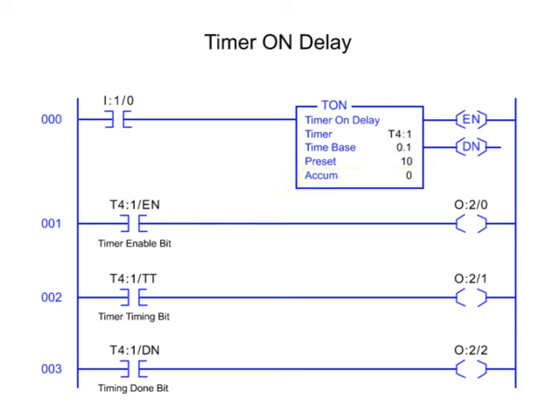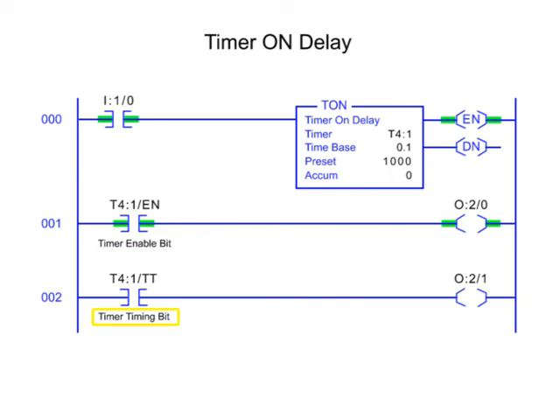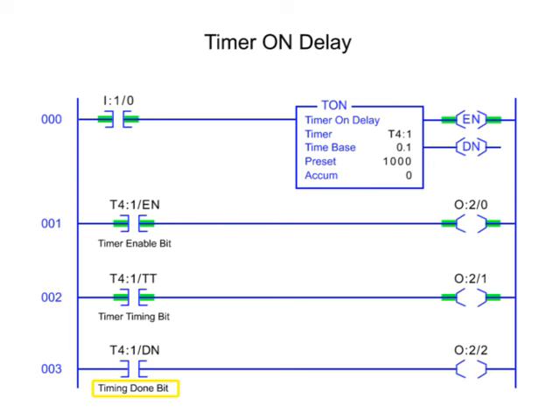For timer instructions, three control bits are available for programming use. Timer enable bit status is true when the timer instruction is true. Timer timing bit status is true when the timer is timing and the accumulated value is changing. Timer done bit status is true when the accumulated value meets the preset value.